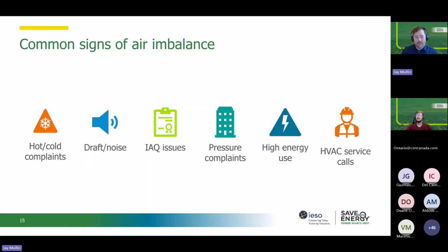The symptoms to look out for that can indicate that there might be a problem are hot, cold complaints across different areas, zones of your facility, because those pressure differentials could be drawing in cold air from outside or hot air from different areas. Drafts, unusual noise, vibrations in ductwork. If there's indoor air quality issues, even though maybe you suspect you should have enough exhaust or fresh air to deal with it. If there's pressure complaints, so doors being hard to open, slamming shut, odors spreading in the facility.